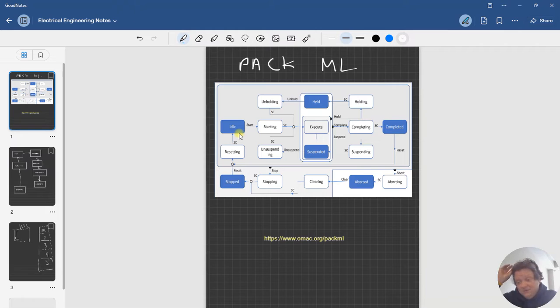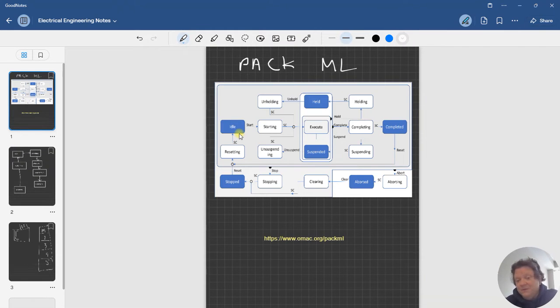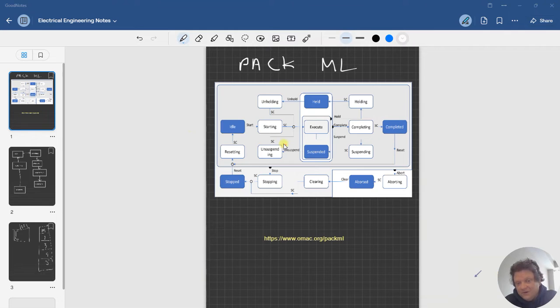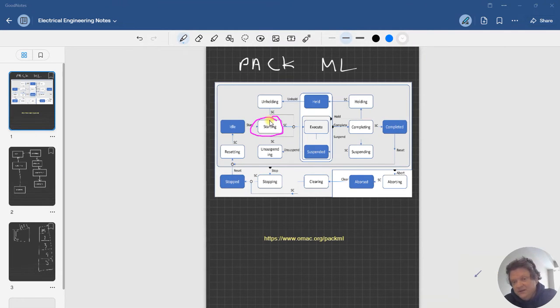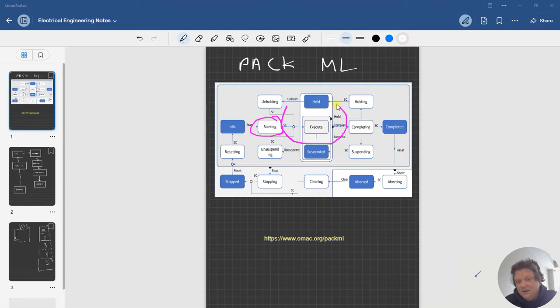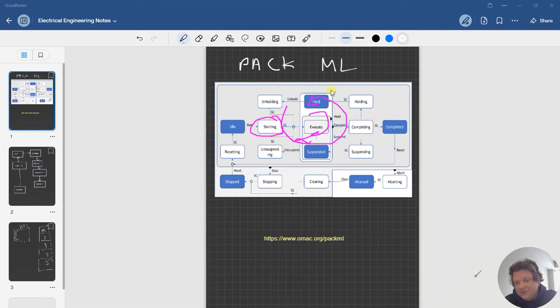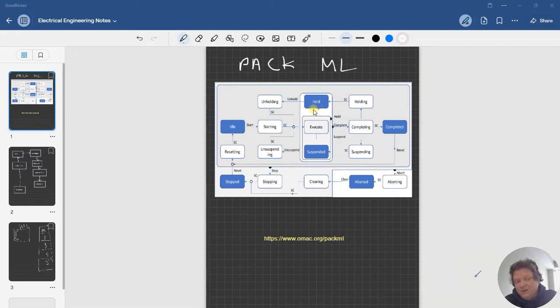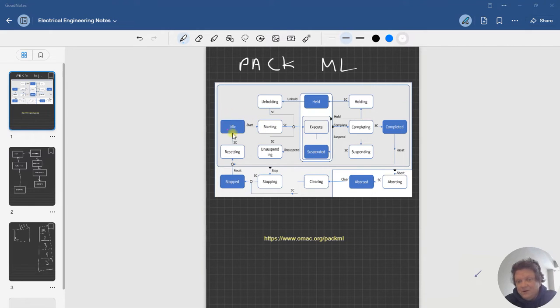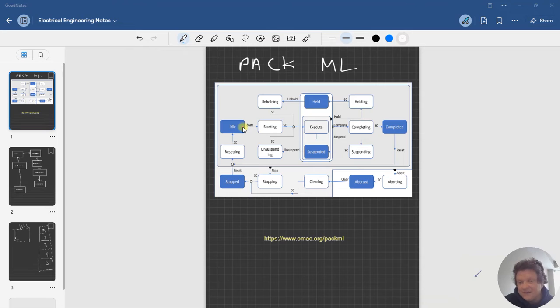The machine should be like in a hold state and that's where you got to transition from the difference between idle and hold. That's where the complexity comes in because some people may see lack of product as idle, other people may see it as a hold. But say my operator is already at the start button and he's waiting on product, then we're doing this. We would go into a hold or suspended because we're waiting on product, and then we don't have to come back over here and physically start the machine again. Those are things that you have to consider in design.